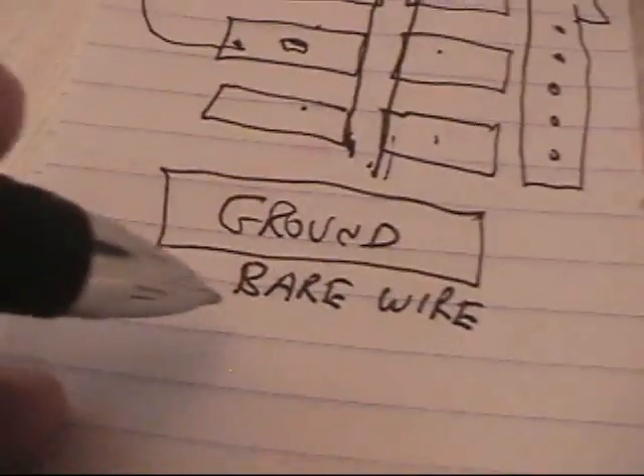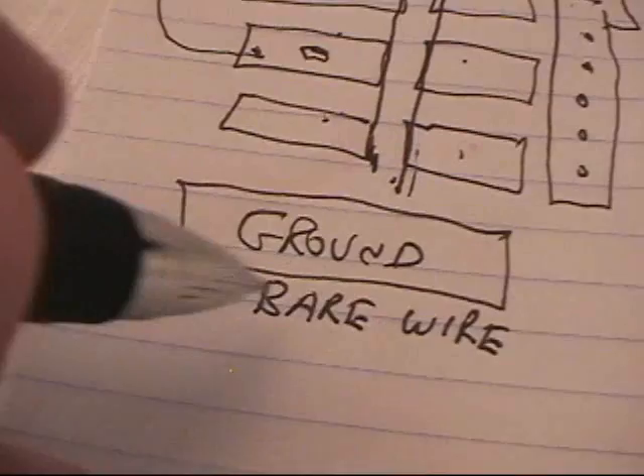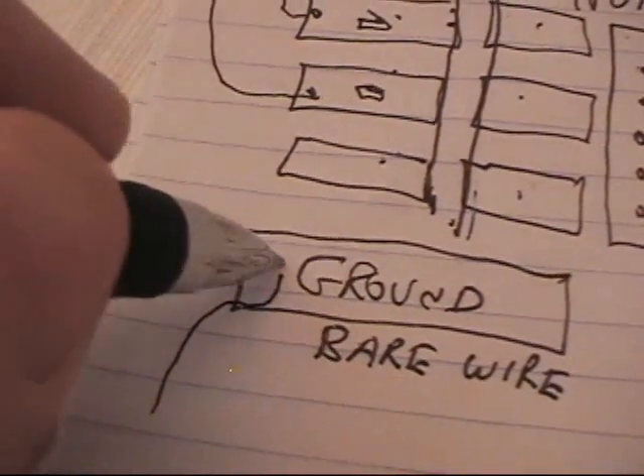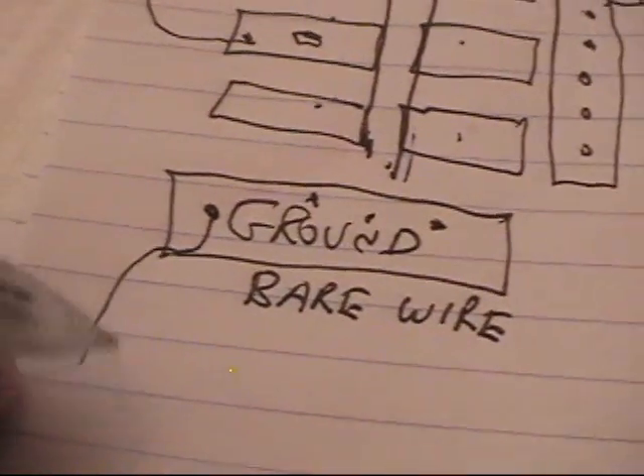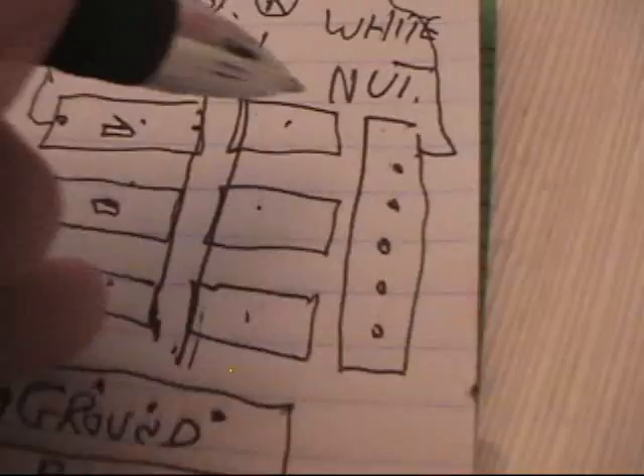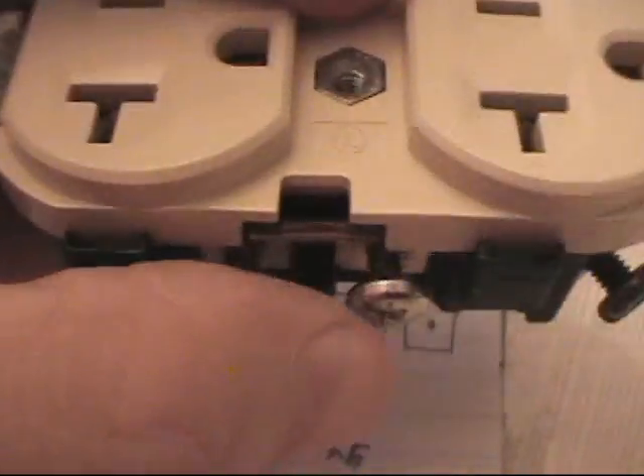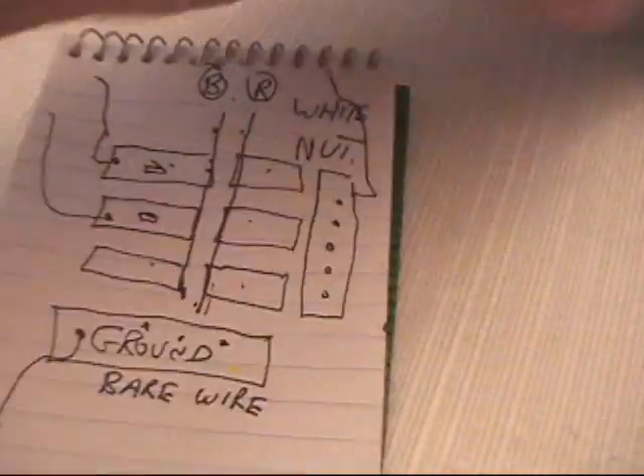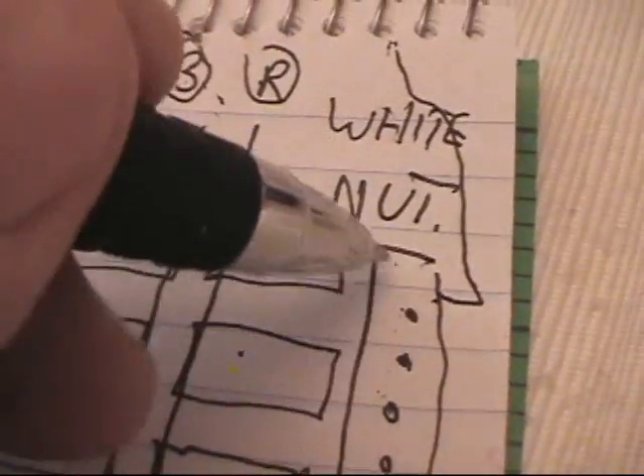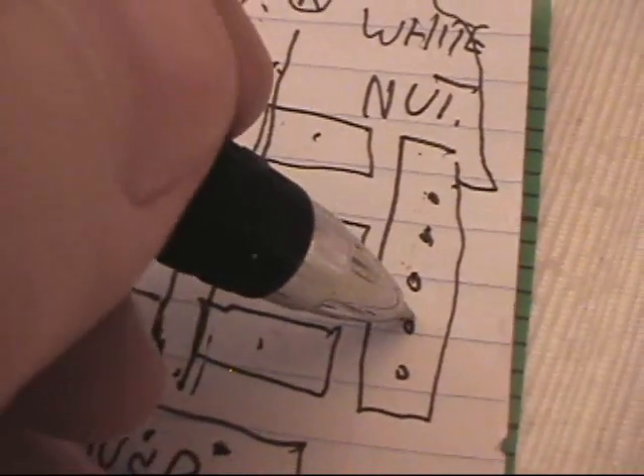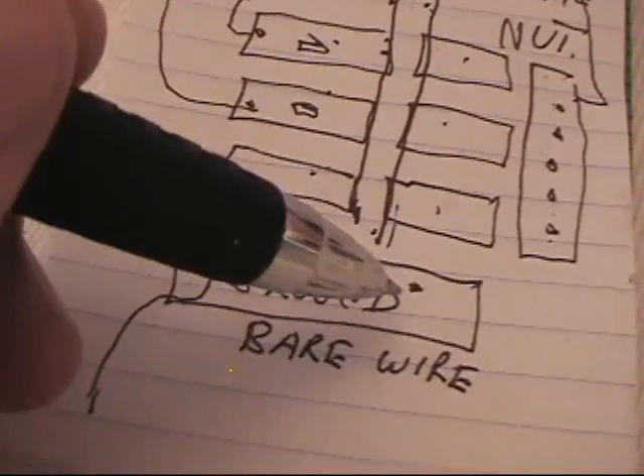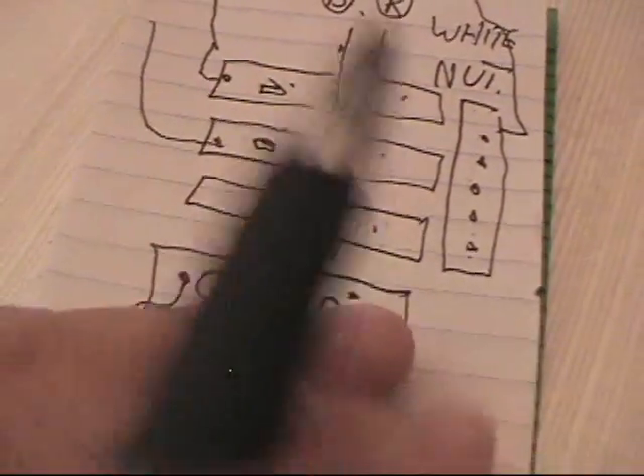Your ground wires is your bare copper wire. That'll just connect under the bunch of screws that are going to be on here, because I'm not a very good drawer. That's why I have to refer to a book as far as drawings are concerned, because I draw like a kid sometimes. And your white wire, your neutral, which is from these outlets and other circuits, not always outlets, they could be lights, are all in here. Each white neutral goes under its own screw. You should not share the screws with more than one wire. All your grounds go on a bus bar, and each one should be in its own screw hole. And if you need more, you just go to the electrical store, and you pick up another bus bar, and you just add it down here.